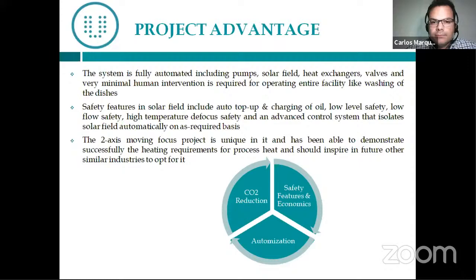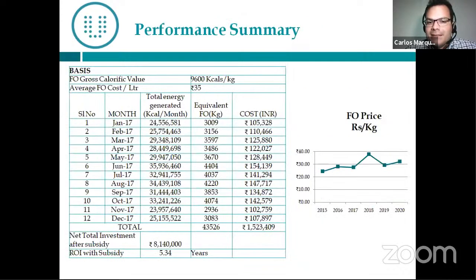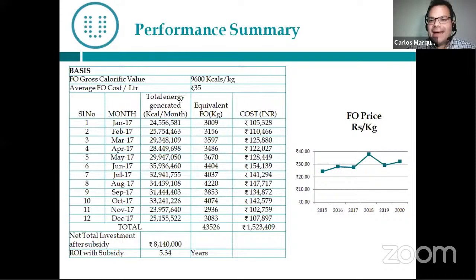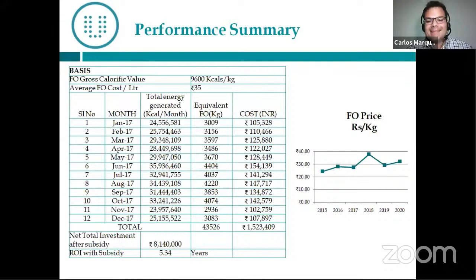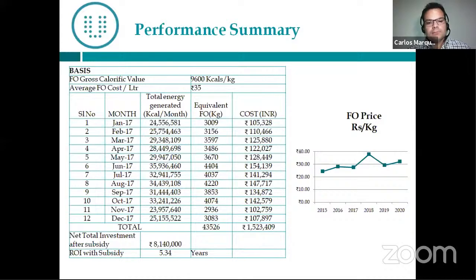The system is eco-friendly, reducing CO2 drastically. In 2017, we saved approximately 43 tons of furnace oil, a benefit of almost 1.5 million Indian rupees. At this rate, the project was depreciated in approximately five and a half years. However, there is a gap between input and yield — we are achieving about 60 percent efficiency at approximately 3 to 5 DNI per day. We need to focus more on improving heat transfer efficiency.